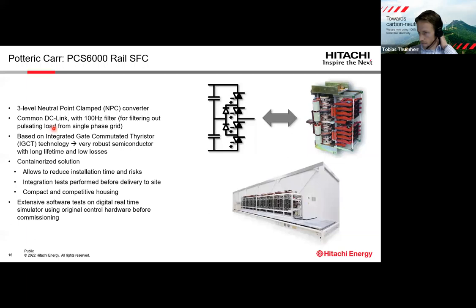The PCS6000 is based on integrated gate commutated thyristor technology, so abbreviated IGCT. This is a very robust semiconductor with a long lifetime and low losses that I think is very well suited for demanding applications like the rail SFCs. Then it's a containerized solution. So I think the main advantages of this is that we can integrate the converter into the container, make the connections, test them in our factory, and then send the whole container on site. And there are only limited connections that then have to be done on site and tested. So this basically reduces the installation time and the risk. And it's also a compact and competitive housing option.